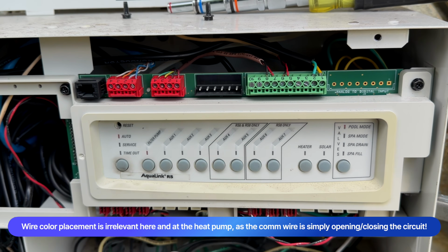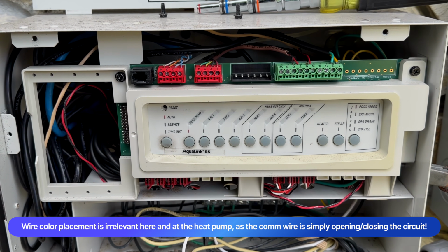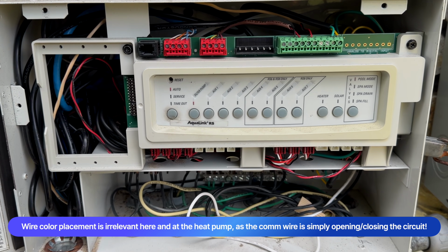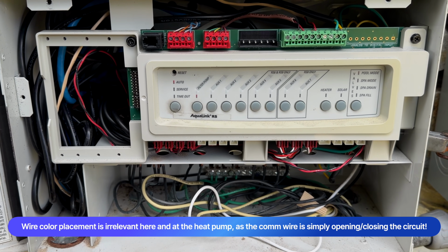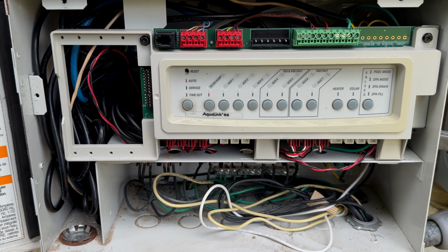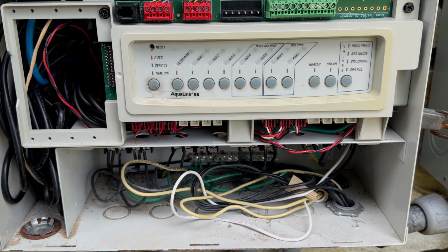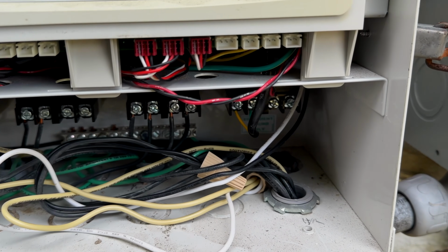If it was a heat only heat pump, you'd be done. But because we have a heat cool, remember those bottom 2 is for the heat cool function—where does that comm wire go? Well, per Gulfstream, that needs to go to an available relay.